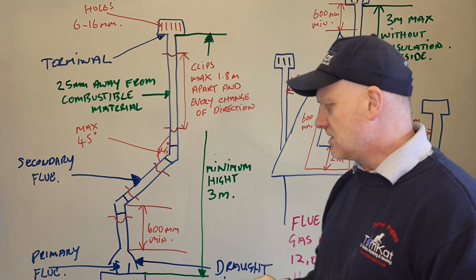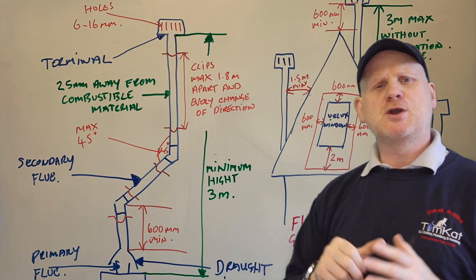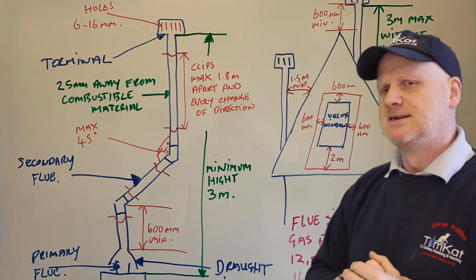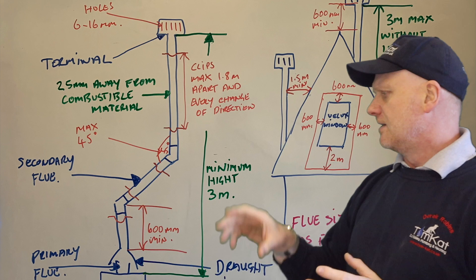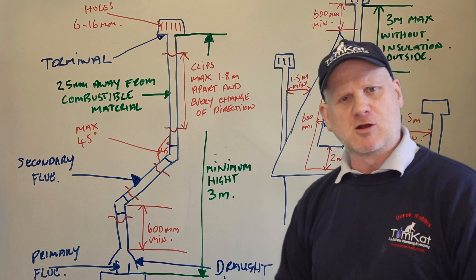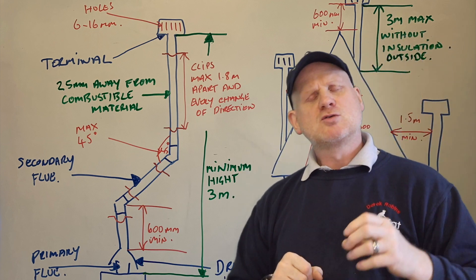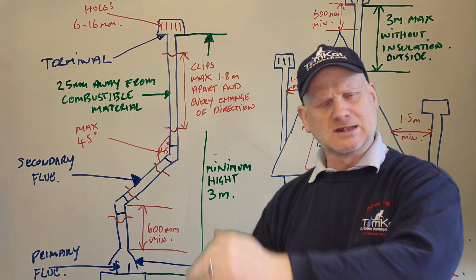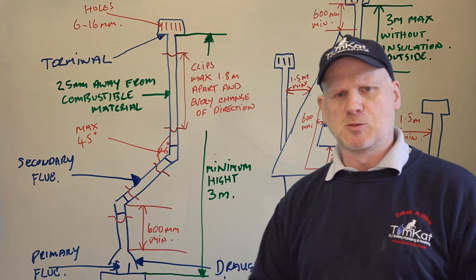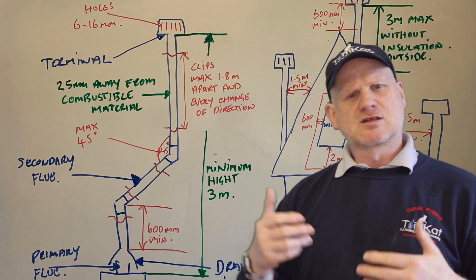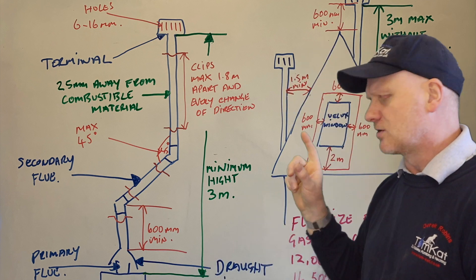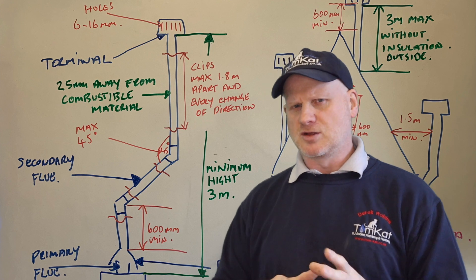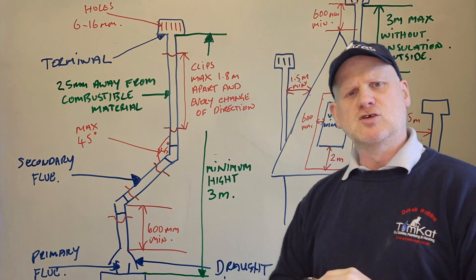For the secondary flue: you must have a minimum of 600mm from the draft diverter to the first bend. After that, flue elbows cannot have more than a 45-degree angle — we cannot have horizontal lengths or 90-degree elbows, as this causes problems with pull and condensation.